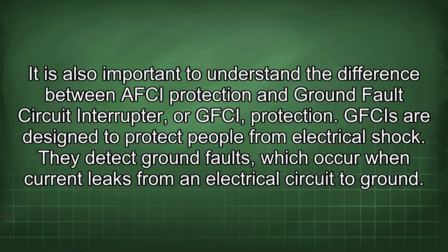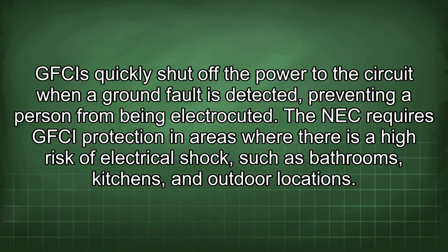It is also important to understand the difference between AFCI protection and ground fault circuit interrupter, or GFCI protection. GFCIs are designed to protect people from electrical shock. They detect ground faults, which occur when current leaks from an electrical circuit to ground. GFCIs quickly shut off the power to the circuit when a ground fault is detected, preventing a person from being electrocuted.